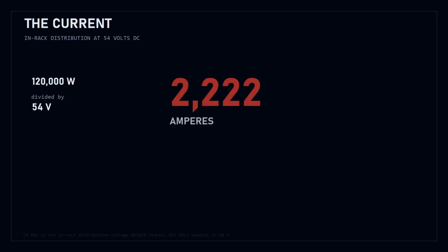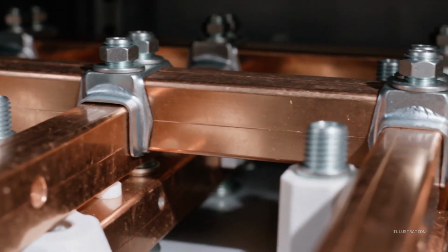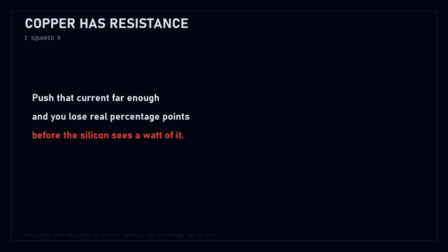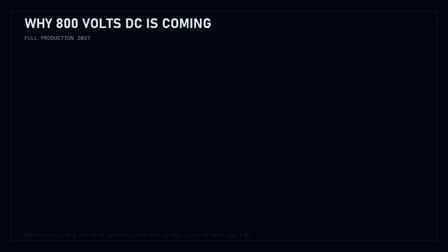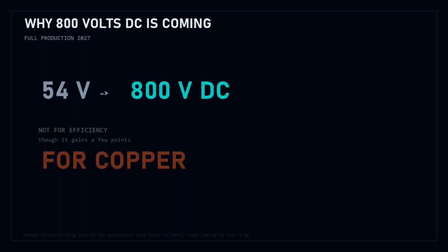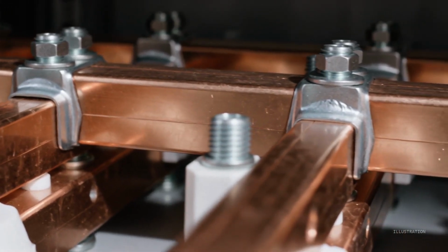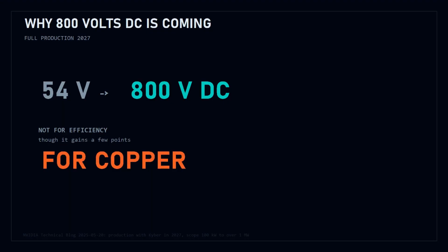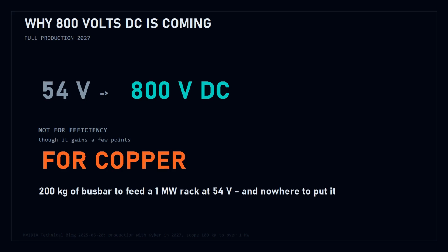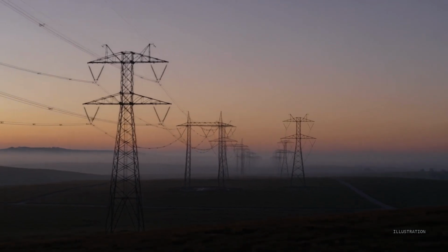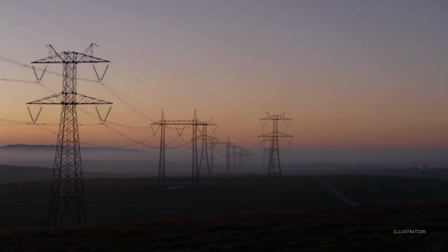120 kilowatts into one rack at the 54 volts NVIDIA distributes in rack is 2,222 amps. That is a bus bar, not a cable. Copper has resistance. Push that current far enough and you lose real percentage points before the silicon sees a watt of it, which is why 800 volts direct current is coming full production in 2027. Not for efficiency, though it gains a few points. For copper, 200 kilograms of bus bar to feed a 1 megawatt rack at 54 volts and nowhere to put it. And one step further out, the constraint stops being electrical engineering at all.